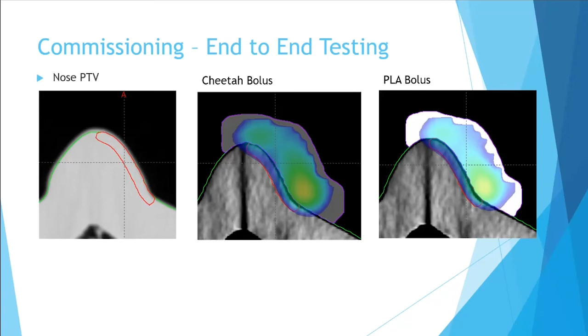So as I said, we printed both of the boluses for the nose and orbit PTVs in both Cheetah and PLA, and we performed surface dose measurements under the bolus using film and MOSFETs, and compared them to those points within our treatment planning system. And we got excellent agreement between the delivered dose and the predicted dose by the treatment planning system. And so this gave us great confidence in our commissioning process and our ability to deliver planned treatments as planned within the system.